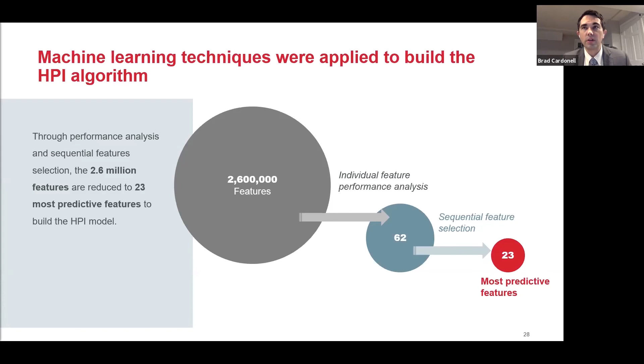So the higher the HPI value, the more likely the patient is trending towards a hypotensive event. I like to think of this as a measure of instability. HPI will increase when it detects more instability from monitoring those specific 23 arterial waveform characteristics, and it does this rapidly by updating every 20 seconds. If we look at this graph here on the right, we see that when the HPI alarm reaches 85, there's about a 93% event rate that'll happen within 4 minutes. So it gives us that time to proactively prevent a hypotensive event.